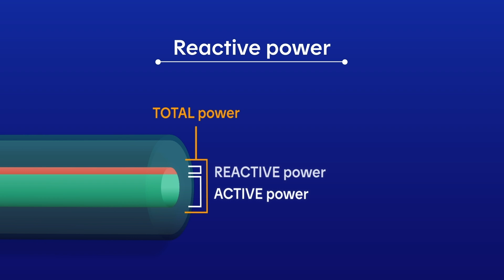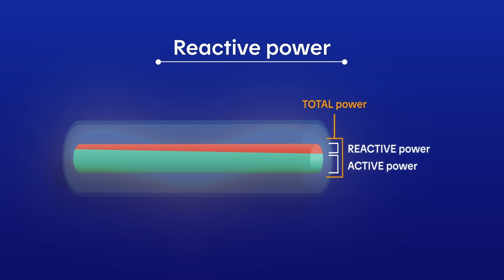The total power is made up of two components: active power, which is used to operate our appliances, and reactive power, which must be limited to ensure the stability of the power system. Underground, everything that surrounds the cable traps the magnetic field, which then increasingly opposes the flow of electricity during transmission and overloads the power system. That's reactive power. The greater the reactive power, the less room there is for active power. In order to transmit more active power, more operating power, the reactive power must be kept to a minimum.